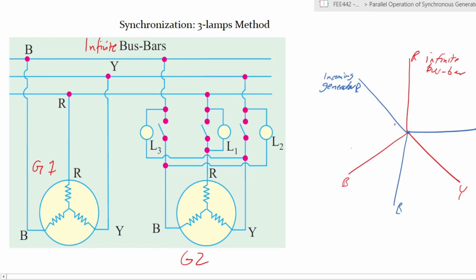So in this case, you now have what we have shown. If this is the phasor of your infinite bus bar in red, right? Your infinite bus bar, which has a generator 1, is in red color over there. And the incoming generator, generator 2, the phasor is in the blue color that we are seeing there. So what you're seeing is the phase sequences are matching each other: red to red, blue to blue, and yellow to yellow. And the incoming generator seems to be slightly ahead of the infinite bus bar, right? So there's a phase difference in between the two.